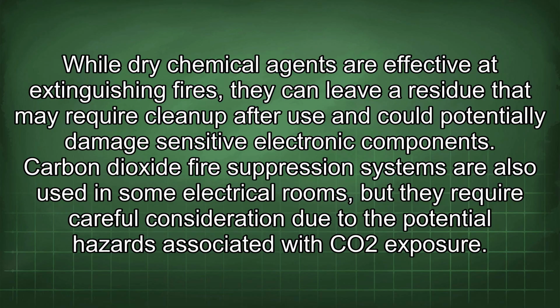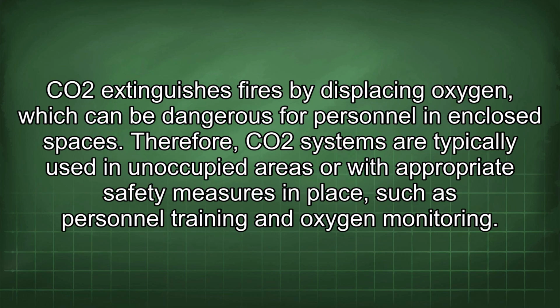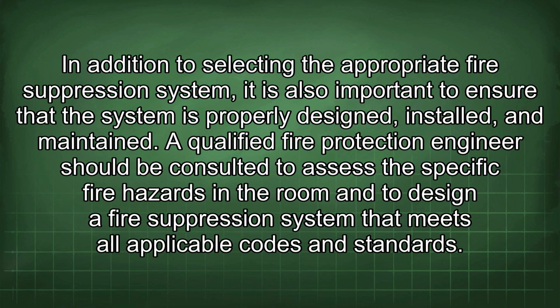Carbon dioxide fire suppression systems are also used in some electrical rooms, but they require careful consideration due to the potential hazards associated with CO2 exposure. CO2 extinguishes fires by displacing oxygen, which can be dangerous for personnel in enclosed spaces. Therefore, CO2 systems are typically used in unoccupied areas or with appropriate safety measures in place, such as personnel training and oxygen monitoring.